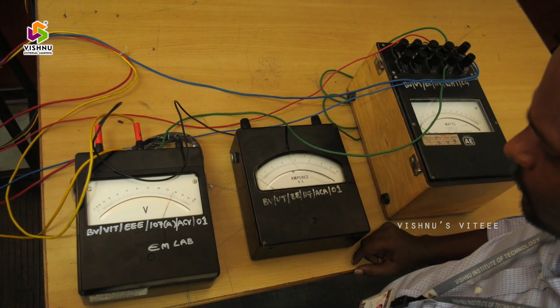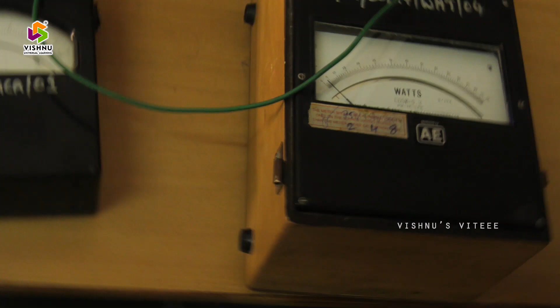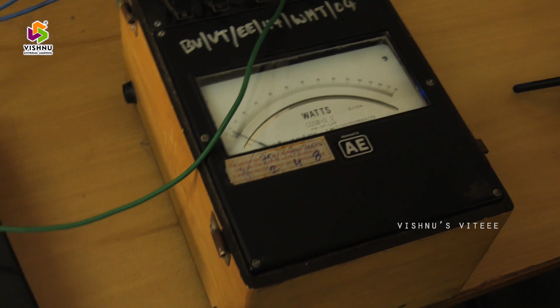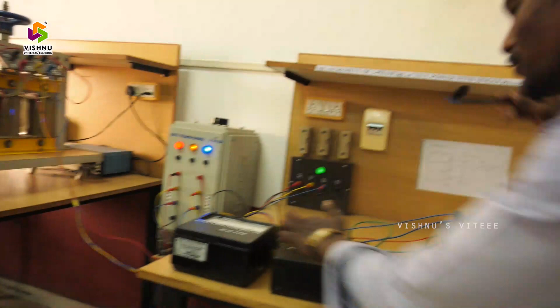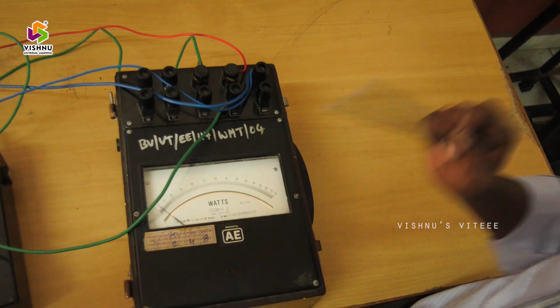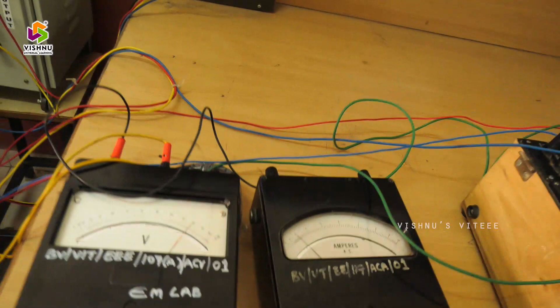Right, students, observing voltmeter reading is 120 volts, and we observe ammeter and wattmeter readings also. Now, plus or minus 6%, observing ammeter reading 2 amperes and wattmeter reading 3 into multiplication factor. Okay, next we are moving from 2 to 2.5 amperes and observing ammeter and wattmeter readings. Here ammeter reading is 2.5 amperes and wattmeter reading is 4.5 watts into multiplication factor. Next, ammeter reading 3 amperes and wattmeter reading 5 watts into multiplication factor.